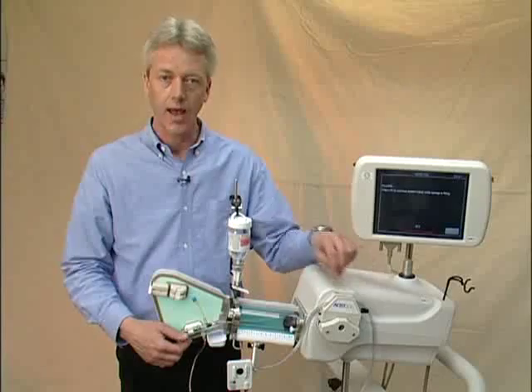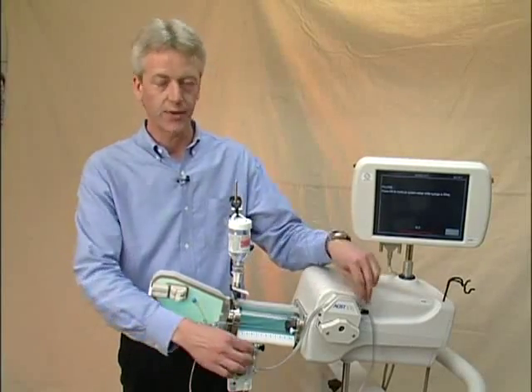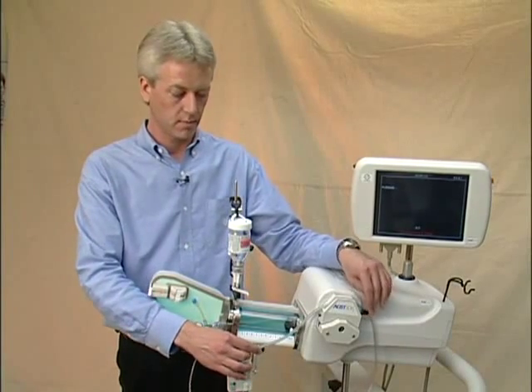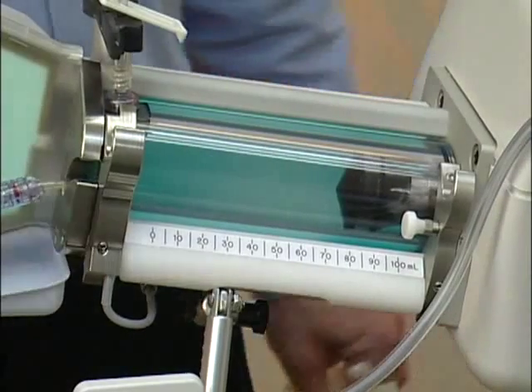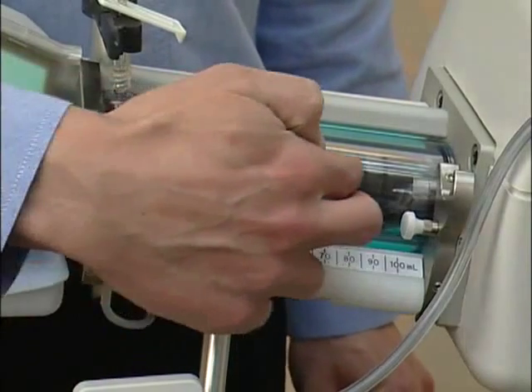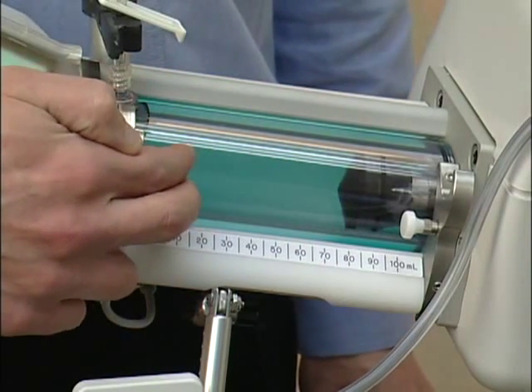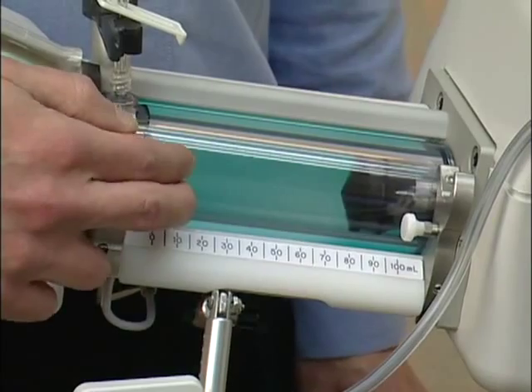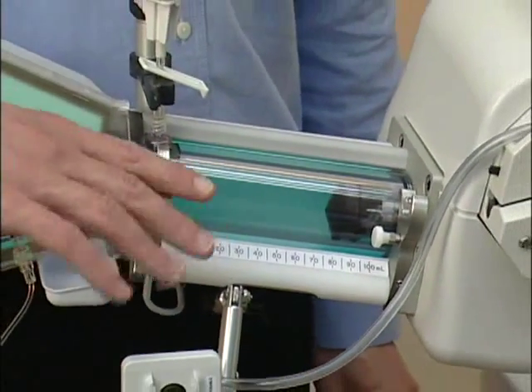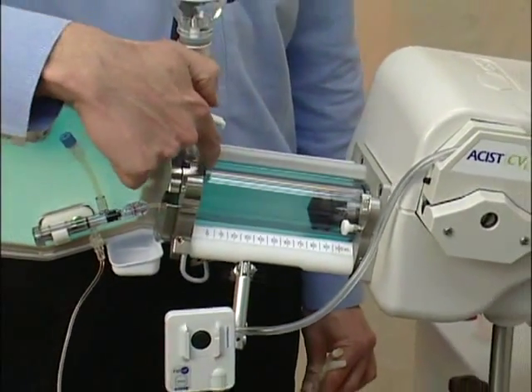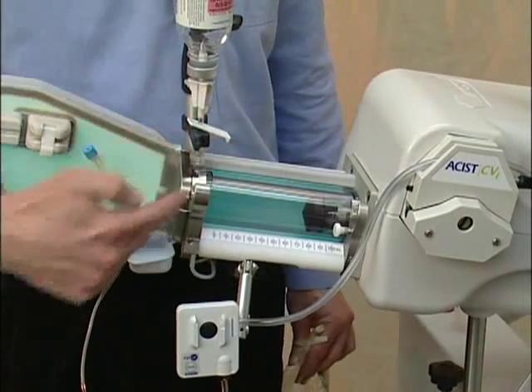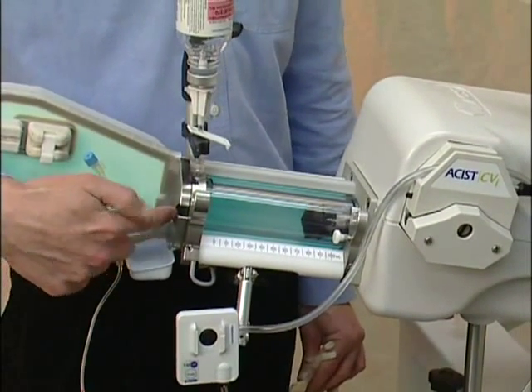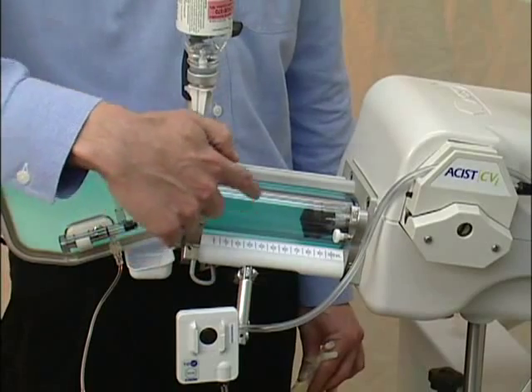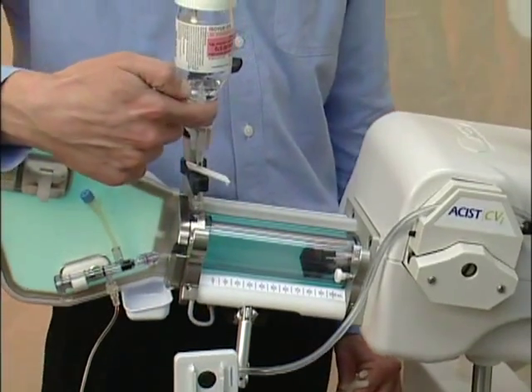The refill begins. As this is happening, I can start with the setup of the saline line and multitask as the system is filling. As the system fills, it automatically purges the air from the syringe. This is done by the angle of the system, which all the air will gravitate towards the top of the syringe, and we inject from the bottom of the syringe. Any excess air in the syringe would be pushed up into the bottle.